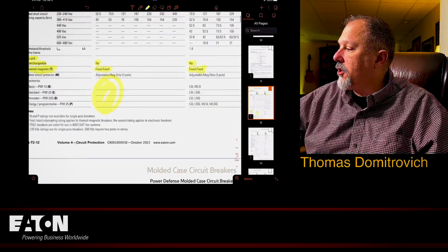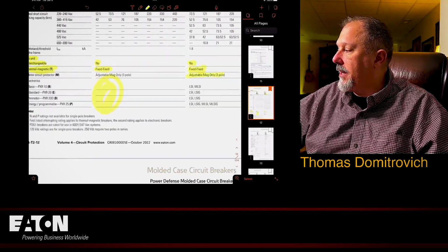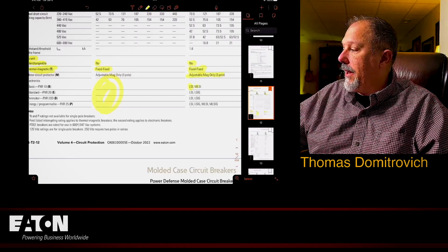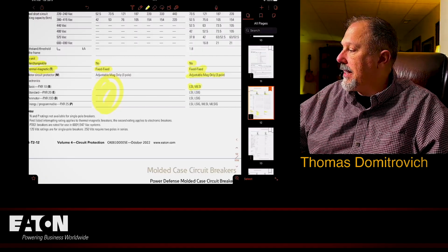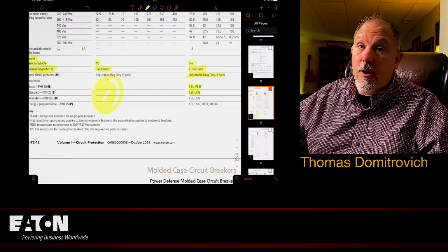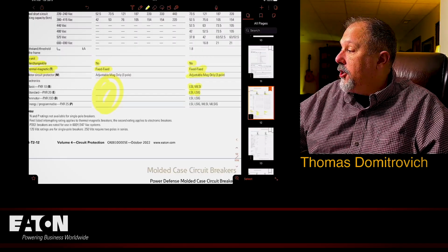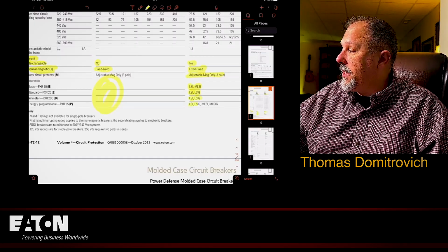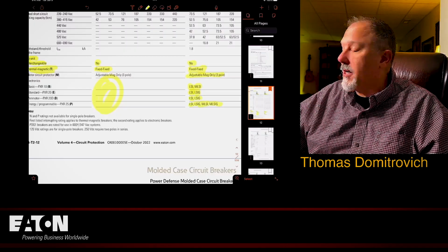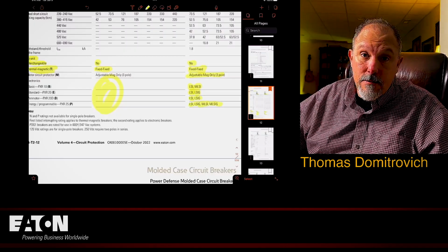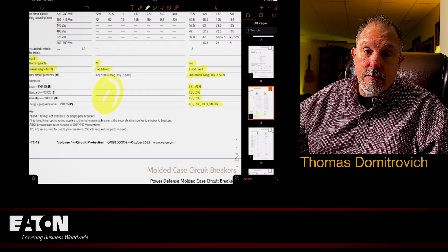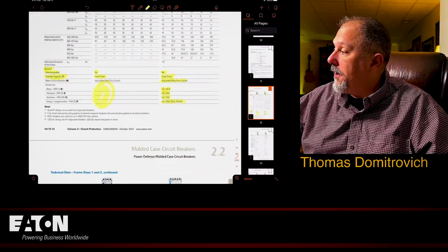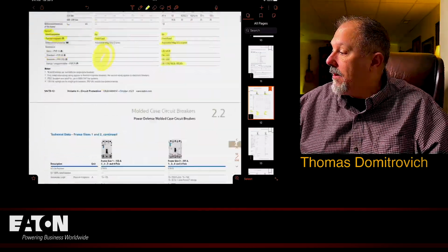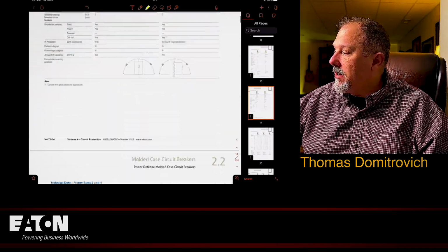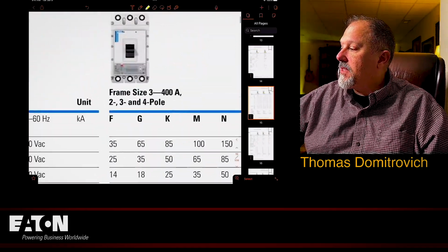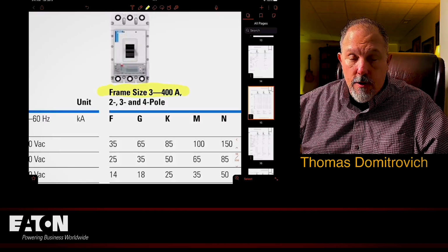And for motor circuit protectors, you have an adjustable magnetic. You have LSI, there's your motor, MLSI, LSIG. You can get ground fault protection of equipment on that. You can get ground fault protection of equipment, and you can get, for a motor circuit protector, some adjustability, but that's it. That's it. You're not gonna find the arc reduction maintenance switch on these two units, right?